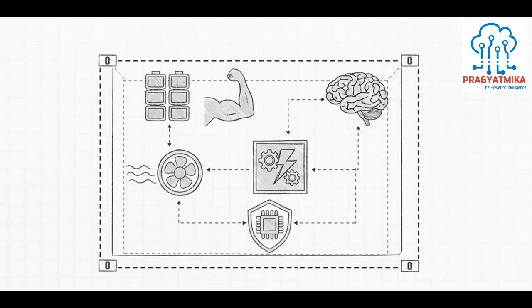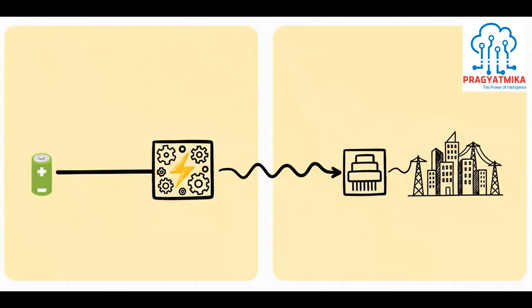Let's look at how all these organs interact. First up, the PCS, or power conversion system. This essentially acts as the digestive system of the BESS. You see, batteries natively store and supply direct current, or DC voltage. But as we know, our electrical grid runs on alternating current, or AC. So the PCS takes that raw DC power from the batteries and digests, or converts it. For example, it might convert it to 690 volts of AC power, which is then fed into a transformer to be massively stepped up, sometimes all the way to 34.5 kilovolts right before it hits the main grid substation. Literally, without the PCS, all that stored battery energy is completely useless to the grid.